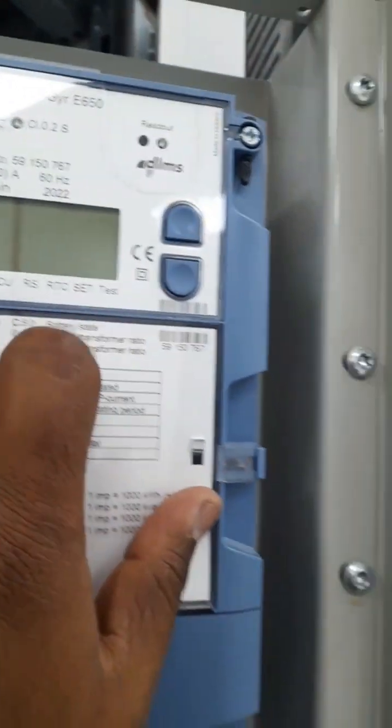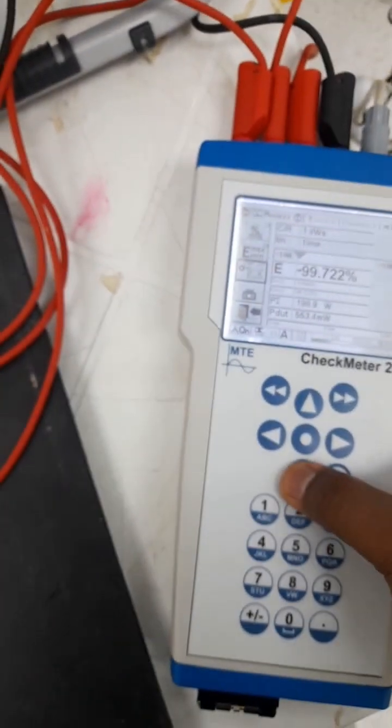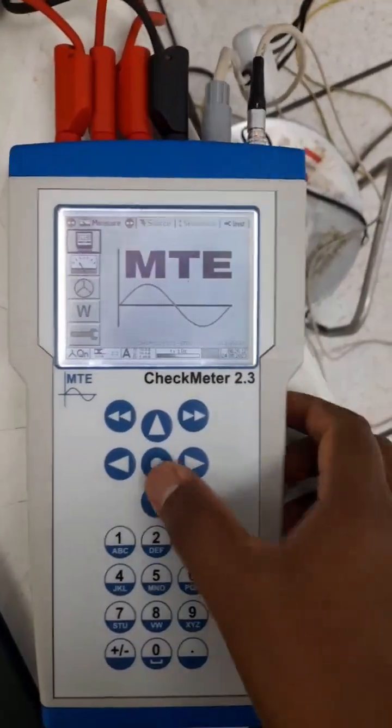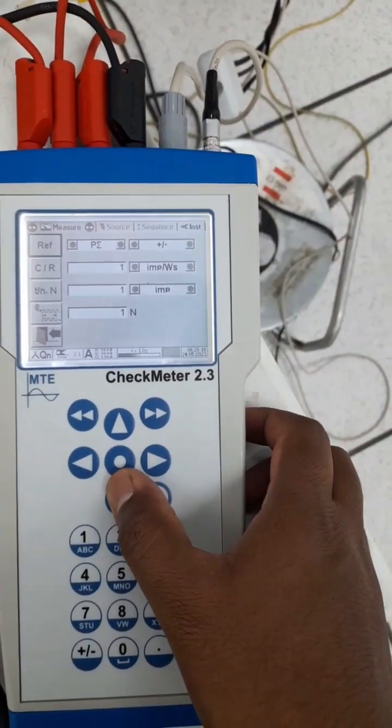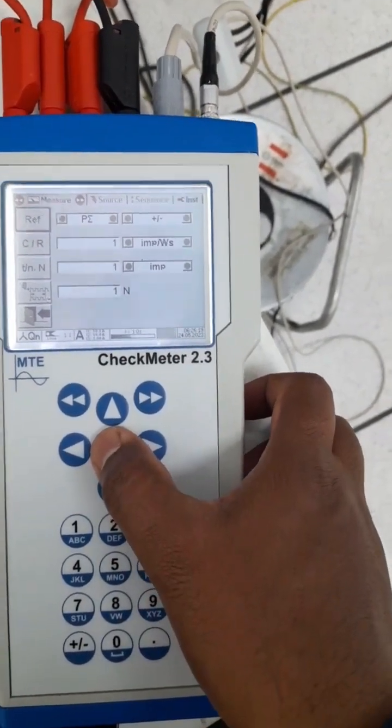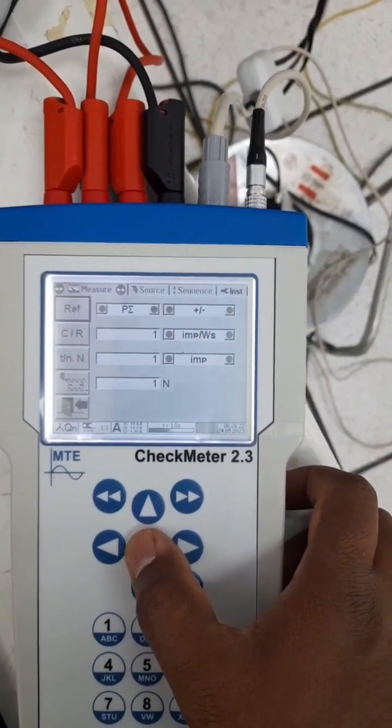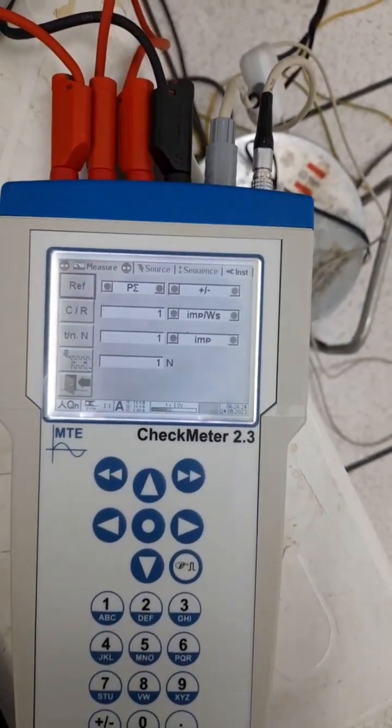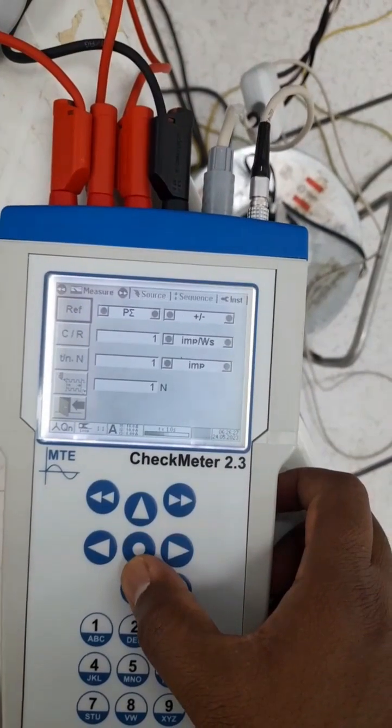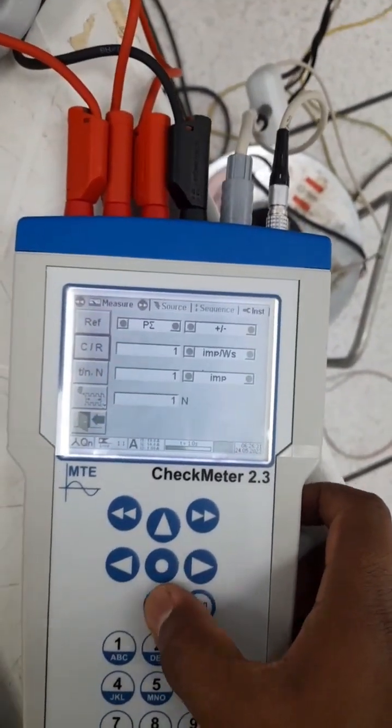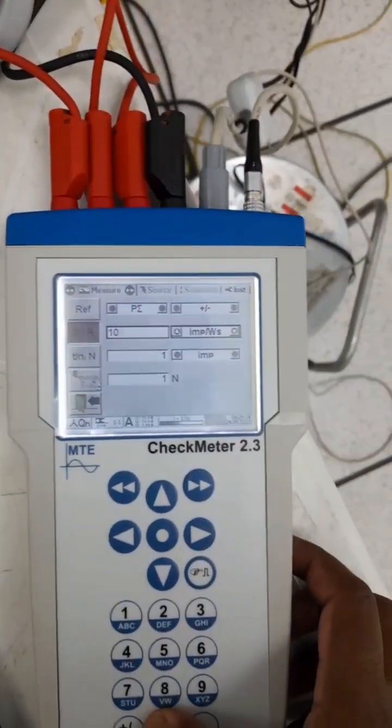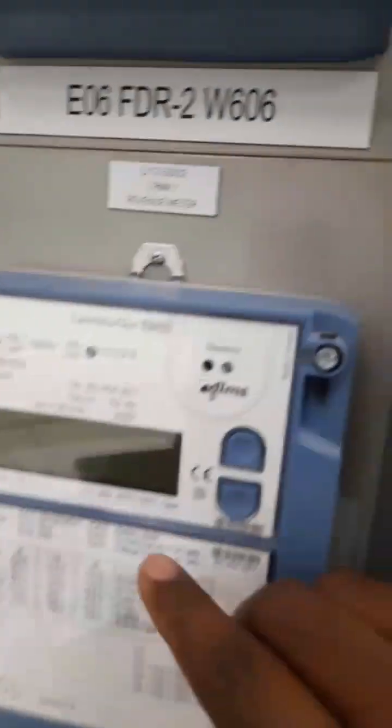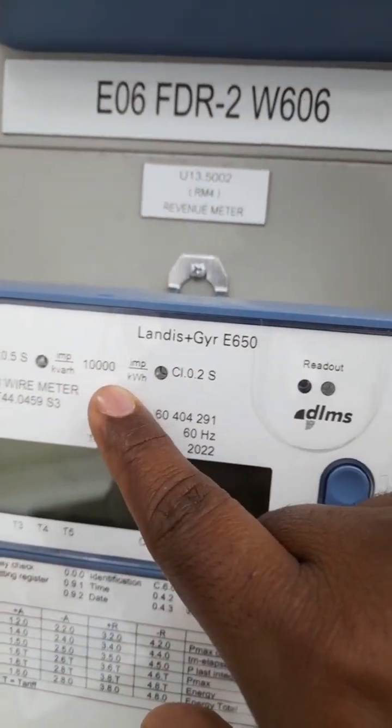This is done. The next will be the kit setup. This is the first page of the equipment. Once you enter over here, just press OK and inside this press enter again. The reference I'm now checking the accuracy for active energy, so the reference must be summation of power. P represents active power. After that, the meter constant you have to enter over here. In my case, 10,000. You can find it from here. The meter constant is 10,000 and my active energy error limit is 0.2 and the reactive is 0.5.